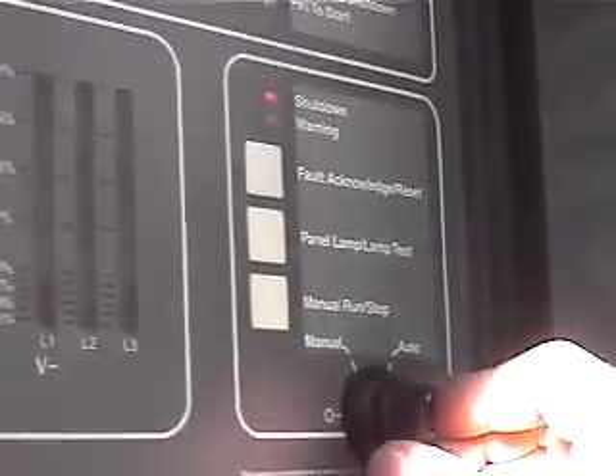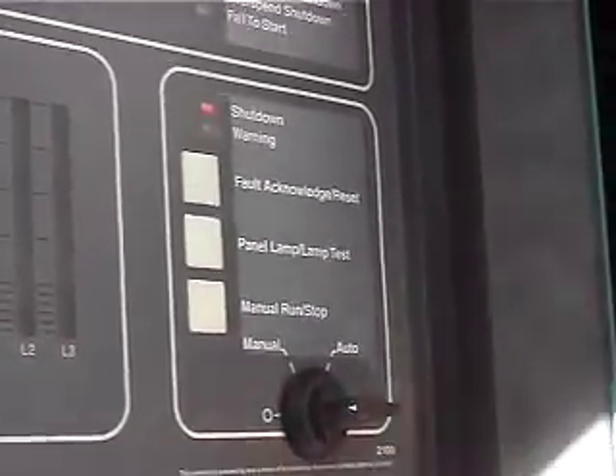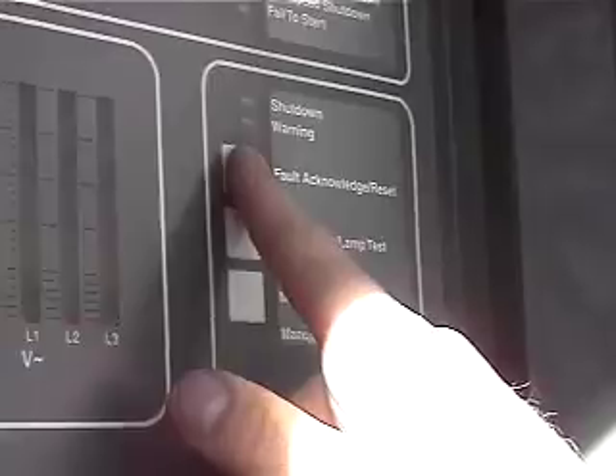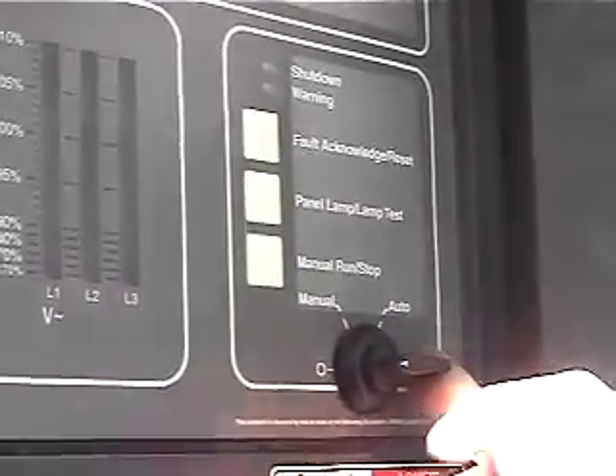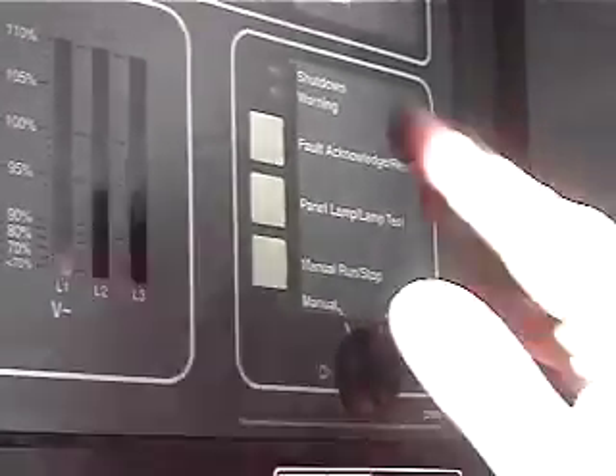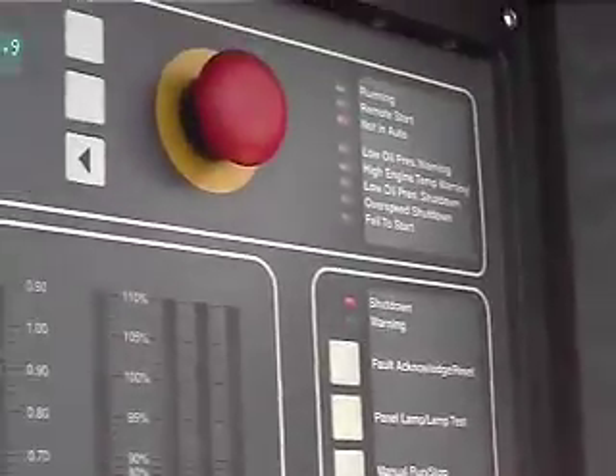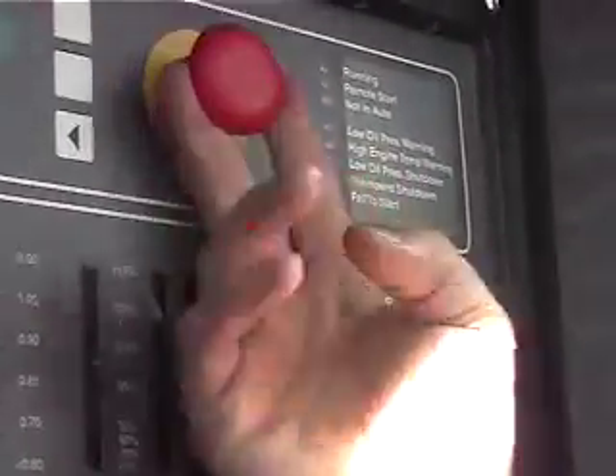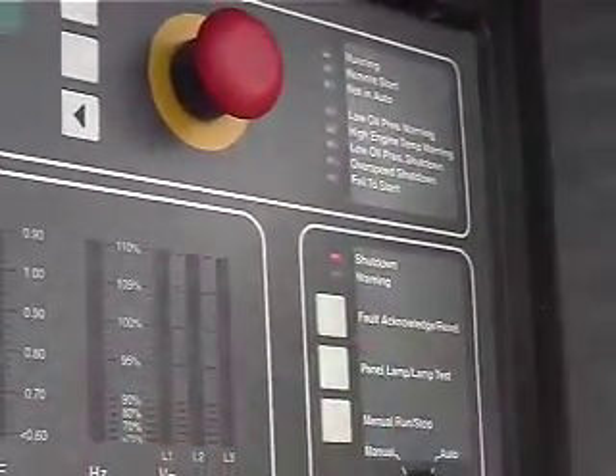So to clear the fault, you have to take this switch to the off position, and then push the fault acknowledge reset button with the switch in off. If you try to reset it with the switch not in off, it will not reset. You can push that button all day long and it won't reset it. So the switch has to be in off, and then fault acknowledge reset. You know it's an active current fault if there's an asterisk on the display of the control panel.